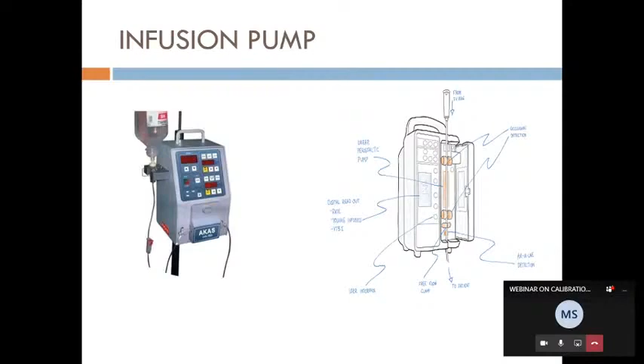Okay, you need to check. You need to check or change the air sensor or the occlusion sensor. As an example, the peristaltic pump is not working. Then you need to check the peristaltic voltages. If correct voltage is going to the peristaltic pump, and even after that the motor is not working, then you need to check the peristaltic motor. The possibility the pump is not working: first thing you need to check occlusion sensor, okay, then air sensor, then peristaltic pump, okay. These are the possibilities.